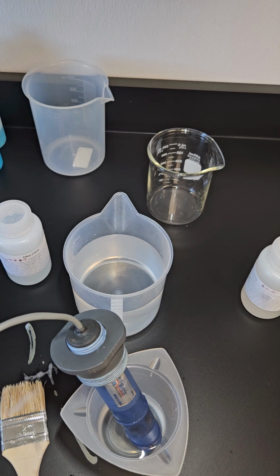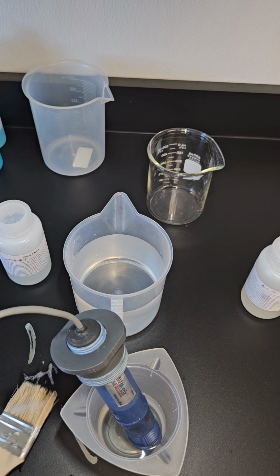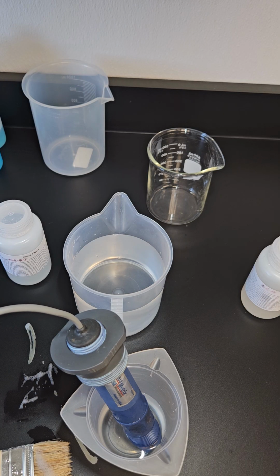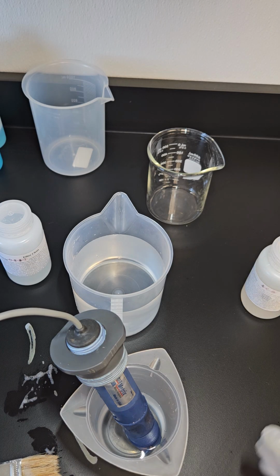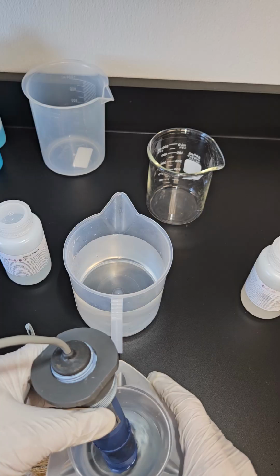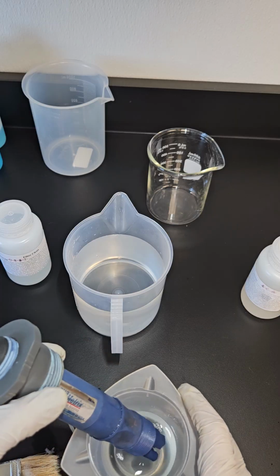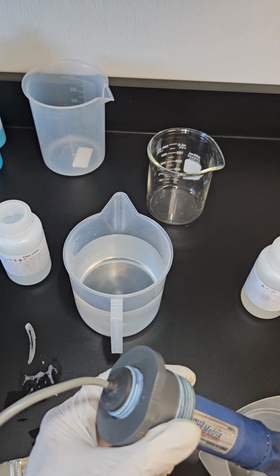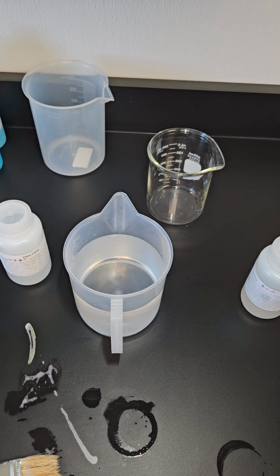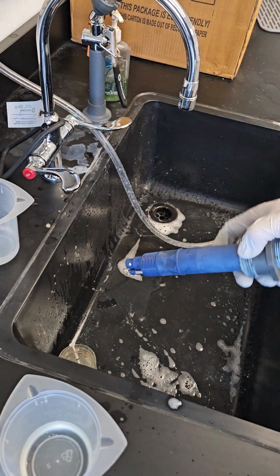But do it every 3 to 6 months, depending on the wastewater that you're treating. Some places have to do it much more often because they use lime in the treatment, so it's going to be a little bit harder water. Other places you can get away with doing this every 6 months or so with the deep cleaning, meaning the acid in addition to the soap and water technique. But a good acid cleaning, I'm not going to do this for 5 minutes, but once that acid has had 5 to 7 minutes to work on that probe, you need to really rinse the acid off thoroughly. So I'll take it back to my sink and run some water on it.